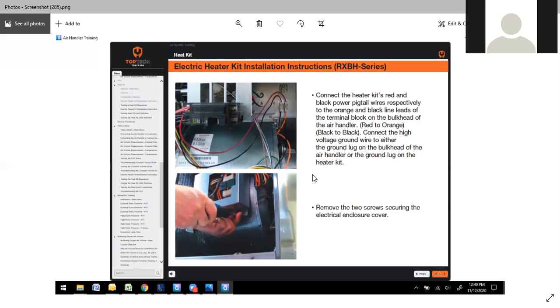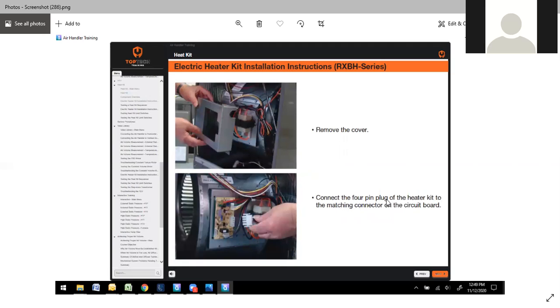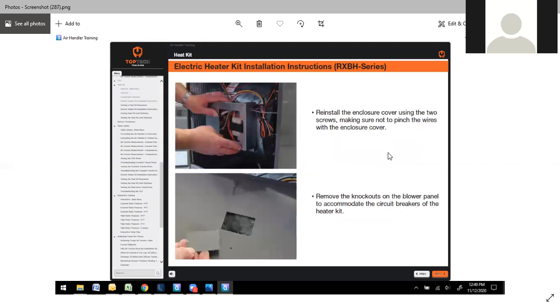Connect the high voltage ground wire to either the ground lug on the bulkhead of the air handler or the ground lug on the heater kit. Remove the 2 screws covering the electric cover box. Remove the cover and then connect the 4-pin plug of the heater kit to the board right here. Reinstall the enclosure, making sure the 2 screws will not pinch the wires. That's kind of a trick sometimes, but if you jockey that around a little bit, you can get the wires safely into the right side. There's a hole cut out there. You can get that plate back on.